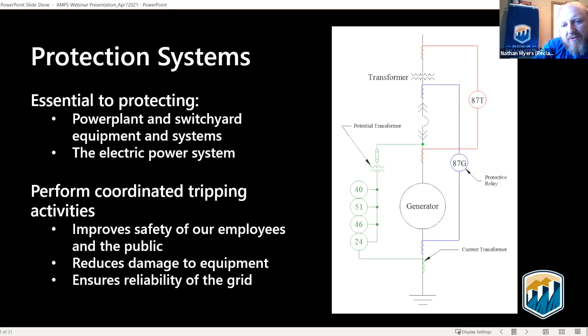So if we were to have a fault on our electrical system, these protective relays measure and record voltages and currents to determine where the fault occurred. Then, using other parts of the protection system, they open the circuit breakers of the affected equipment, preventing or reducing damage to that equipment.